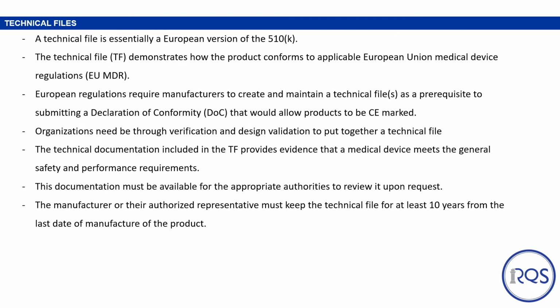Let's now discuss technical files. A technical file is essentially a European version of the 510(k). The technical file, or TF, demonstrates how the product conforms to applicable European Union medical device regulations, also known as EU MDR. European regulations require manufacturers to create and maintain a technical file or files as a prerequisite to submitting a Declaration of Conformity, or DOC, that would allow products to be CE marked.